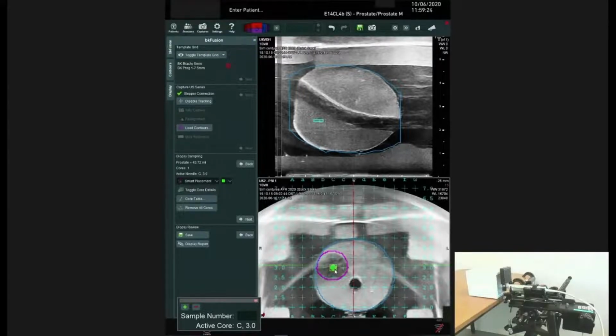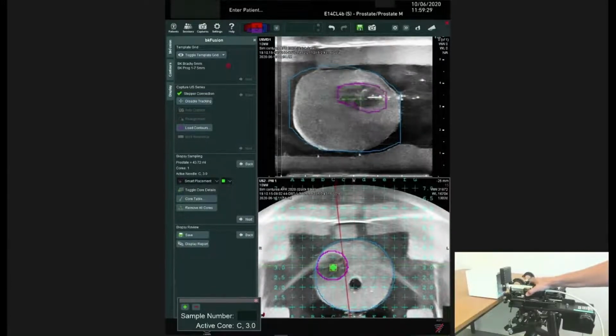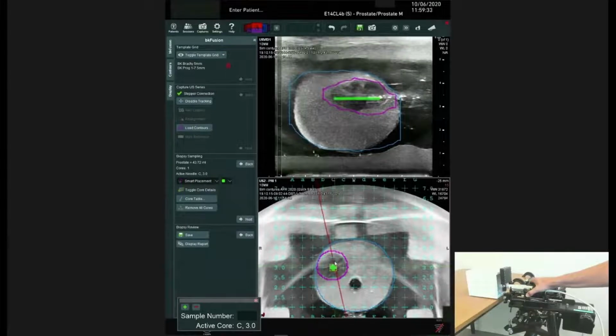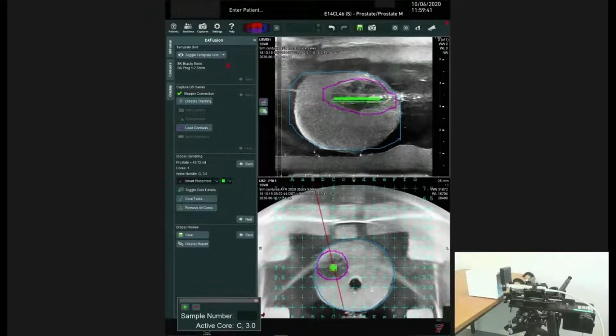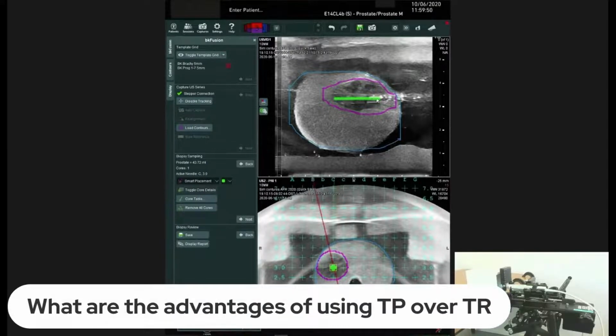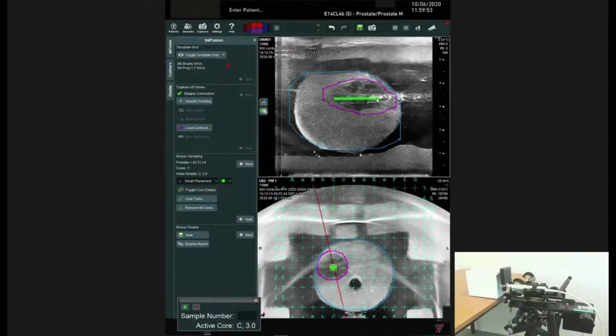Next, you'll rotate the cradle so that you'll turn the transducer array toward the target in the sagittal view. As you rotate the cradle, you'll see that the line moves on the transverse image and that the virtual core will appear on the sagittal image. Keep in mind this is a virtual core that we are using to pre-plan where it is that we want to biopsy. You can see on the sagittal image that the virtual core is a solid green. This means that you have not actually done the biopsy yet. Once the biopsy has been done, we will document this by marking where the sample was taken. More on this in a few moments.